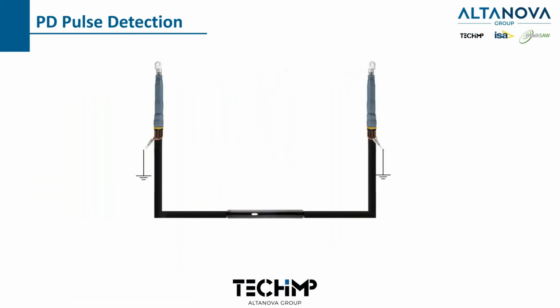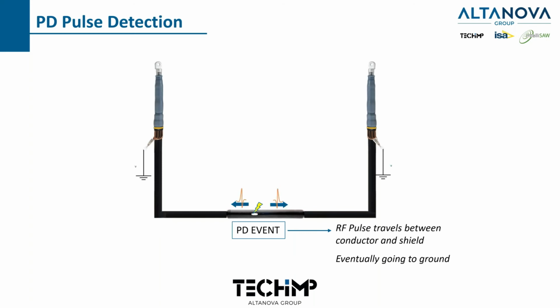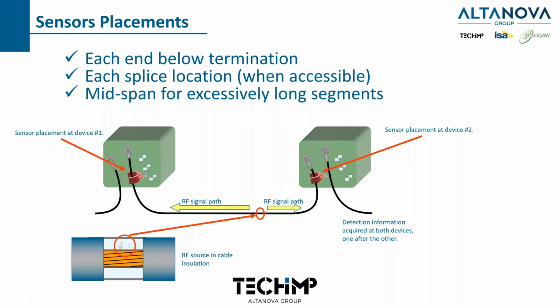So here's a little graphic to help you understand what we're doing here. We have a PD event going on in this splice right here. So the technicians will come in and start placing sensors. There's the PD going to ground. That picture's a little misleading. We'll start at one end, place a sensor, and then we always like to get a measurement on each side of the splice. So they'll place either an HFCT or a UCAP on each side of the splice, pick up those RF signals, and then they'll send that information to the lab.